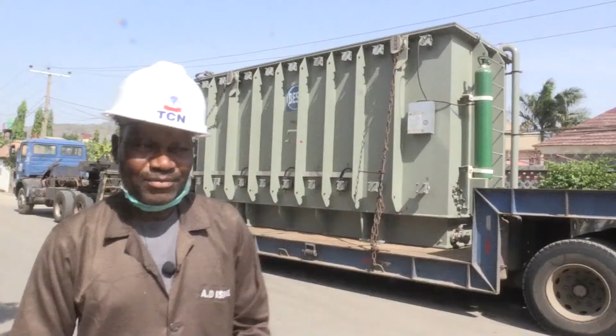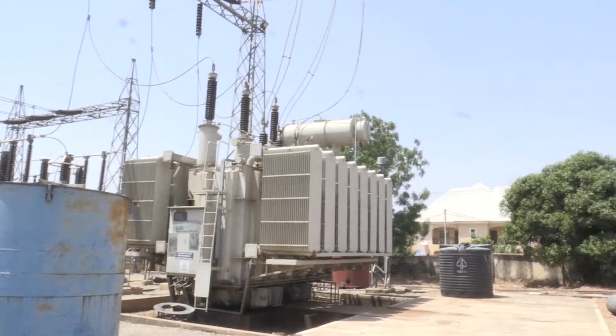Abuja metropolis actually, so I happen to be in the main city of Abuja. The capacity of the substation before was 120 MVA. Unfortunately, around the 5th of October last year, we had an unfortunate incident where one of the transformers was faulty as a result of failure. So we had to disconnect and decouple that transformer, leaving the station with only one, that is 60 MVA. Before, we were having 2 by 60 MVA, making 120 MVA.